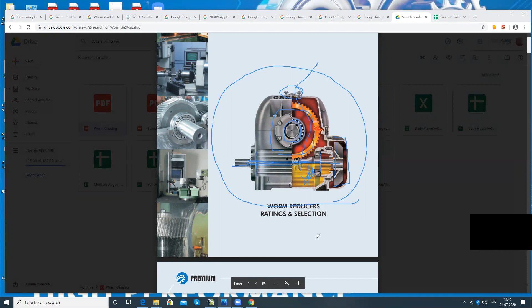Then I can show you some other points as well. This is called the fan cover, made of plastic. This is the fan, also made of plastic. The fan is on this shaft itself, so it moves at the same speed as the worm shaft. Here there will be a coupling, this will be the motor shaft, and this will be the big motor. So this arrangement has a coupling in between. A worm gearbox 99% of the time will have the motor foot mounted on its foot, and this will be the output shaft of the motor, the input shaft of the gear, with a small coupling in between.